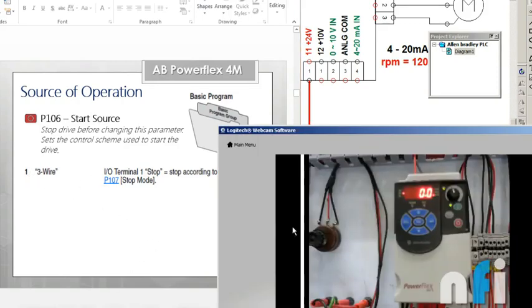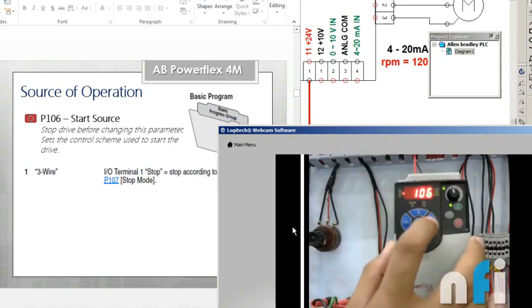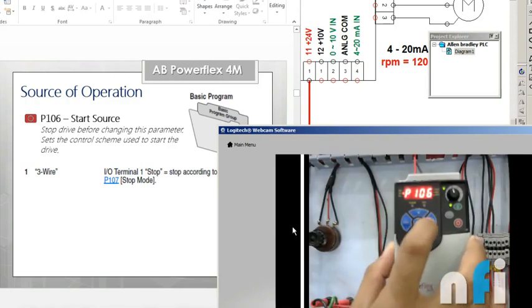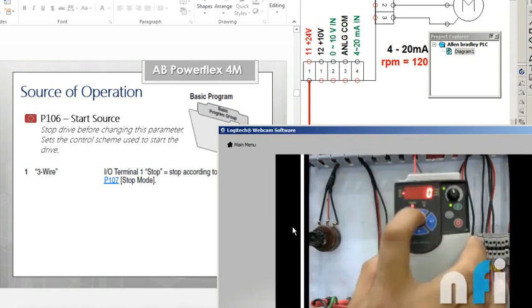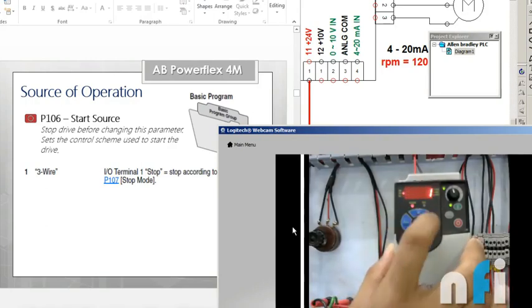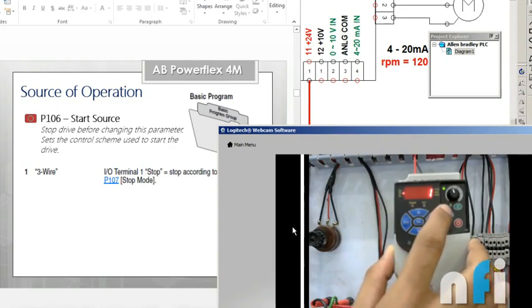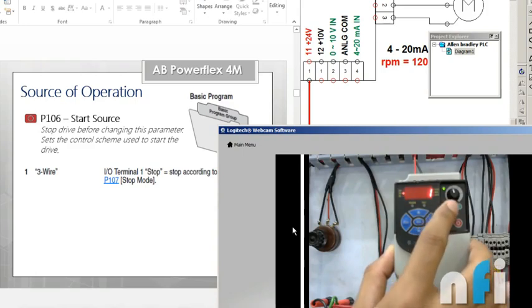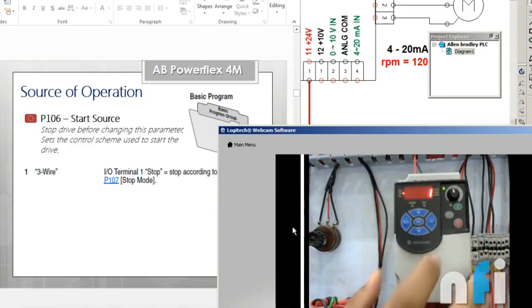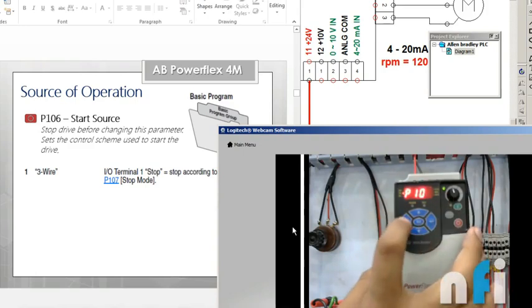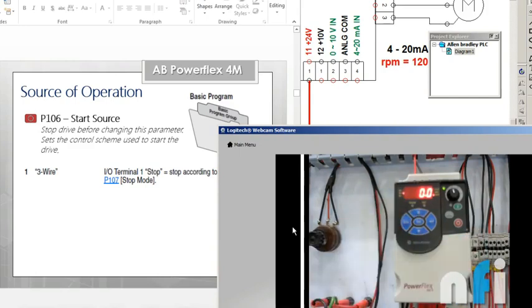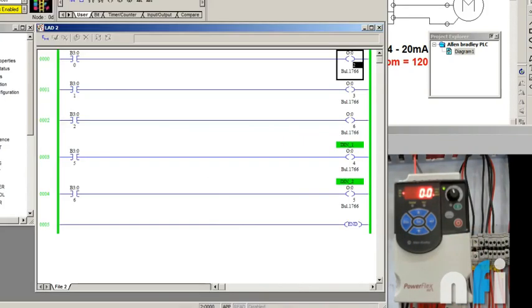So that's the parameter here, 106. Go inside and enter one. This is one, press enter again. As soon as I press enter, you'll find this LED goes off because now the control has been shifted from this control keypad to external control. So I'll go back here. This is the frequency. Now let's move to PLC and see how this is working.